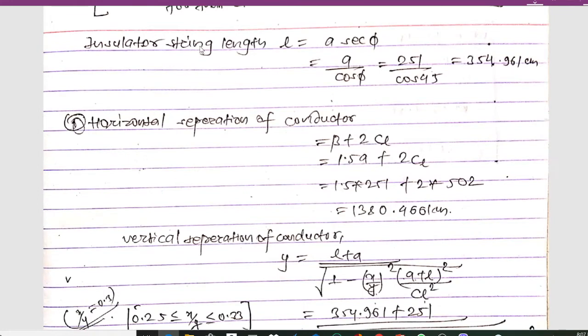The insulator string length L is calculated using the formula L = A / cos φ. With A = 251 centimeters and φ = 45 degrees, we get: L = 251 / cos 45° = 354.96 centimeters.